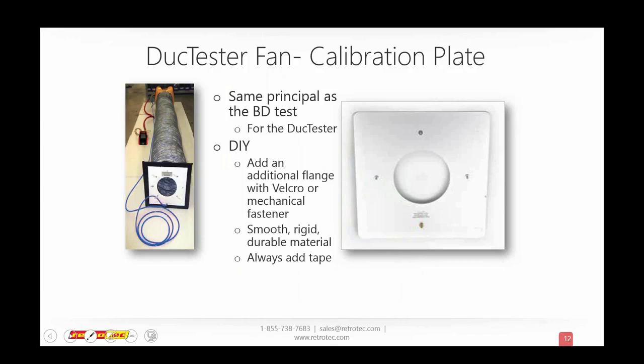Good point. Yeah, if I didn't mention it earlier, I do want to mention that one of the great things about the DM32 is that it can give you all kinds of results right in the gauge. So you're not tied specifically to just CFM or pressure, Pascal usually. So here what we actually did was instead of testing for pressure at flow or pressure at CFM, we're actually going to test for pressure at equivalent leakage, and you can do per square inch, you can do per square centimeter, but the point is that, like Colin said, when you cut your hole, if you make your own hole, you could cut it 10 by 10, and then you know that you should have an equivalent leakage of 100 square inches or centimeters. And I completely agree that if you're not testing to a specific code or some kind of specific standard that means that you have to use that, it's probably easier to understand.